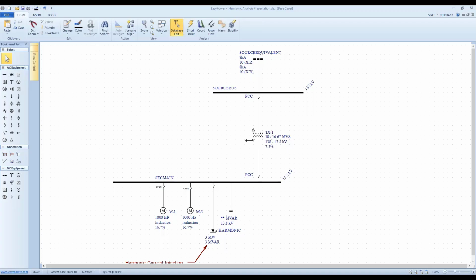Okay, so in this regard, I always model my harmonic sources as being completely in phase. In other words, I do not assign phase angles to my harmonic current injections. But with that being said, when you have a 12-pulse device, say a rectifier or VFD drive, there is phase angle cancellation between the two 6-pulse bridges within that rectifier, and that cancellation can be modeled outright, or it can be assumed.